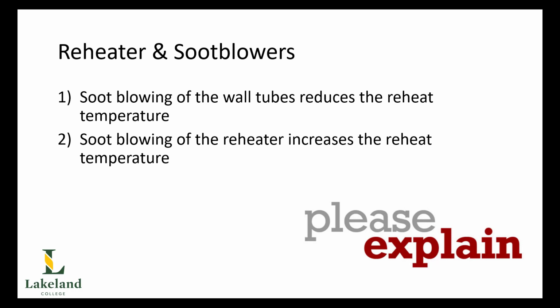So if our reheater has got some ash on it and we now blow it off, well, it's now going to be free to absorb more heat, because that layer of ash or soot takes the form of like an insulating blanket, thereby reducing our heat transfer capability.